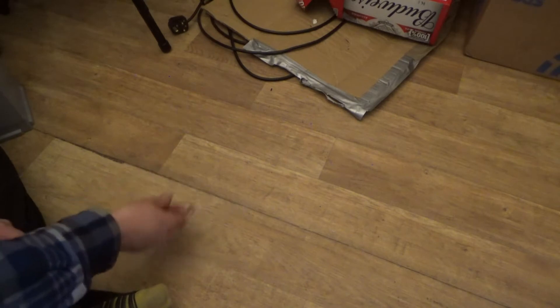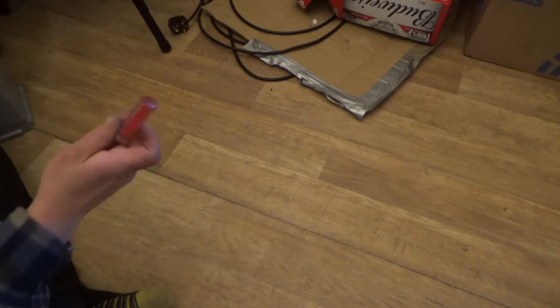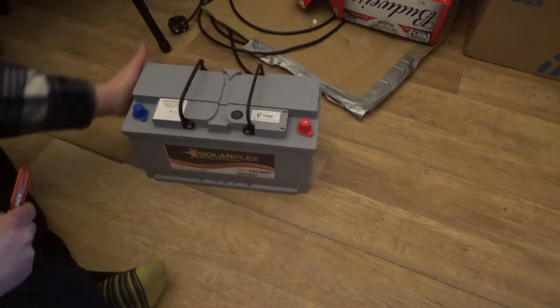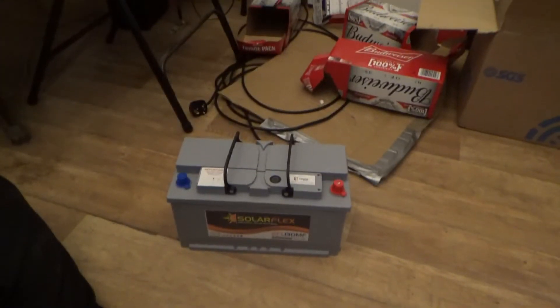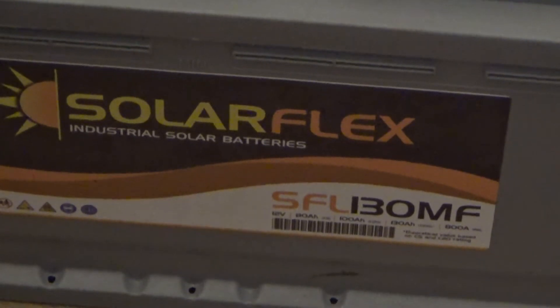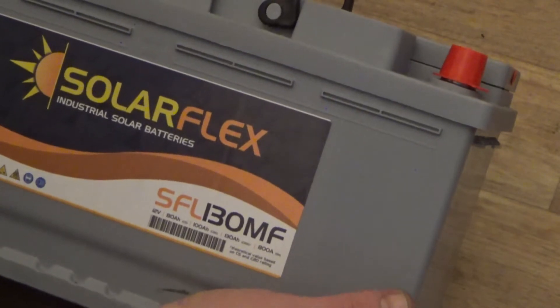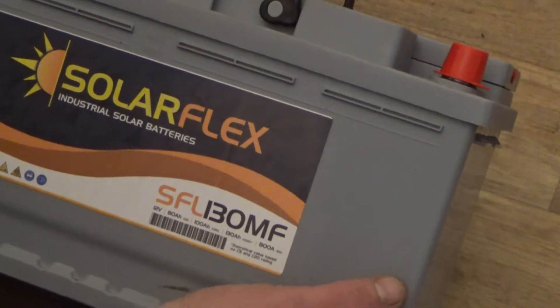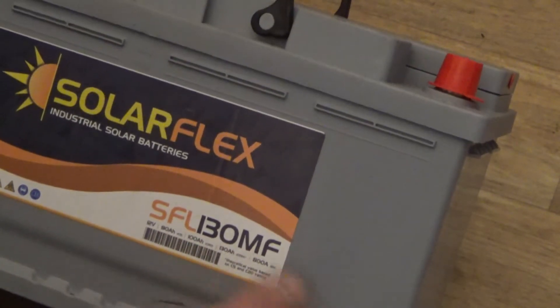Hello everyone, welcome to the channel. Today's video is a capacity upgrade for the battery bank for the solar system. I've got a Solar Flex SFL130MF from Tayna Batteries — a 12-volt battery at 130 amp hours. It's rated at 80 amp C5 and 100 amp C20, which basically means the capacity varies depending on the draw rate. My system is 24-volt.